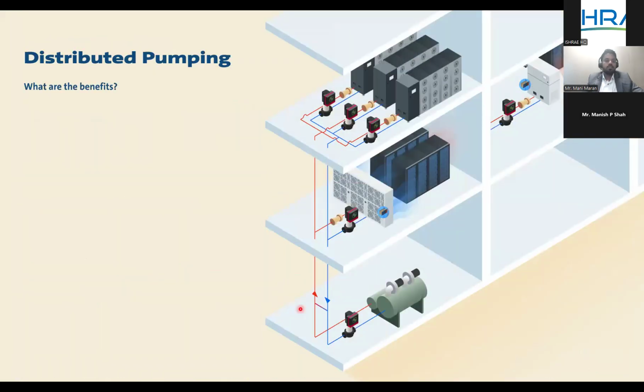So coming back to the benefits, from the pain points we have discussed with the variable primary system or variable secondary system, it will definitely reduce the pumping energy consumption, because we are removing the unnecessary friction created in the system, but still we deliver the same performance in a much more efficient way. And since this is a temperature driven system, the multiple complexities of the pressure based system are removed, which will further reduce the energy consumption of the pump. The balancing becomes much easier between primary and secondary, and that gives the advantage of maintaining the delta T closest to the design most of the time.